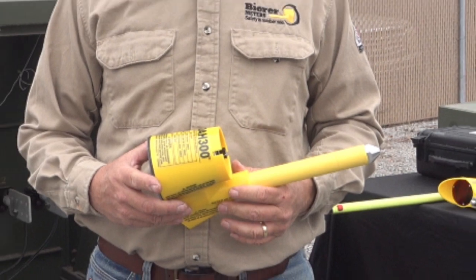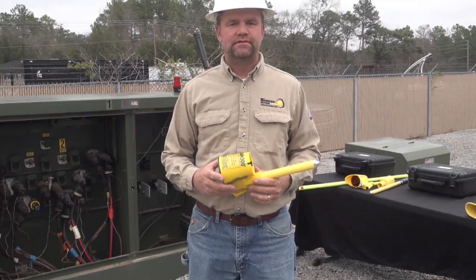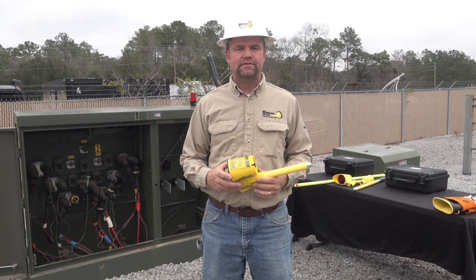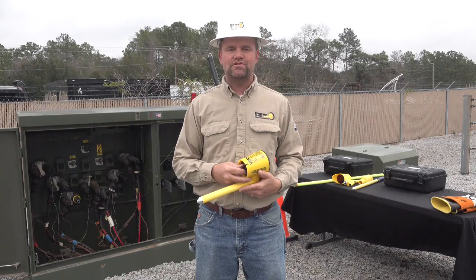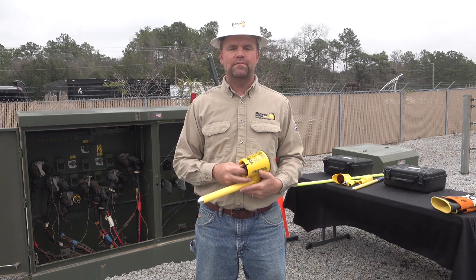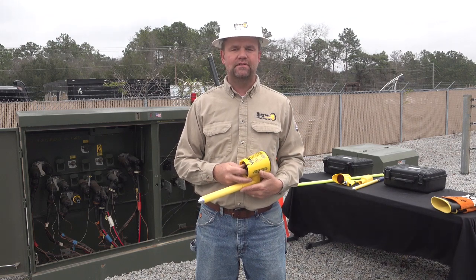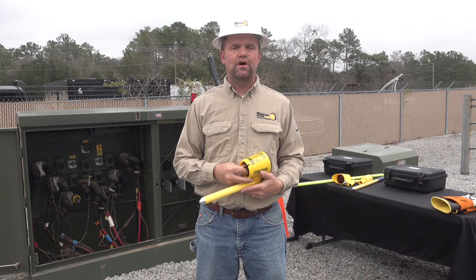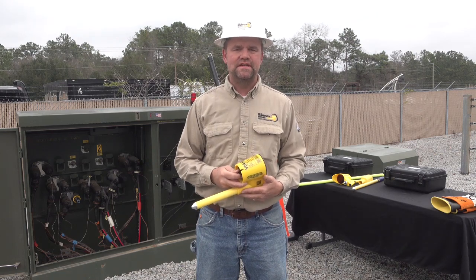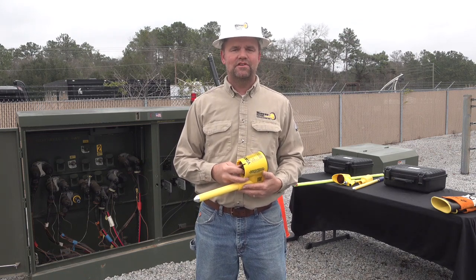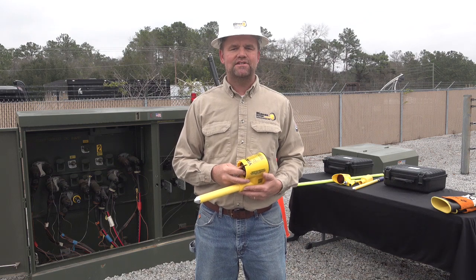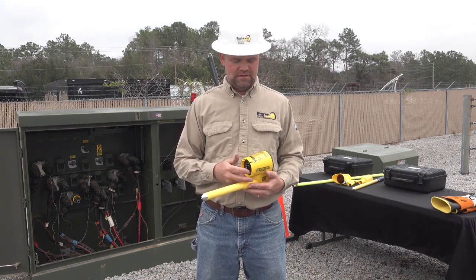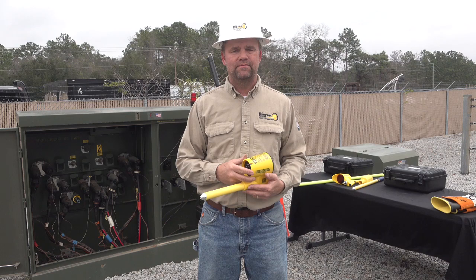Type 2 means it has a numeric display with or without an audible alarm, and Style B designates that it can be used outdoors. The VDAH300 is a linear logarithmic analog voltage detector. The V stands for voltage, the D stands for detector, the A stands for analog, and the H stands for hold. This device does have a hold feature.